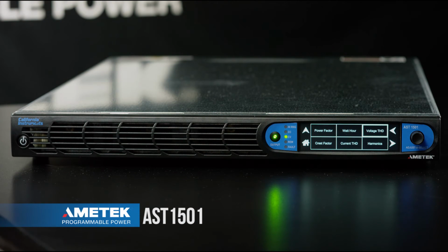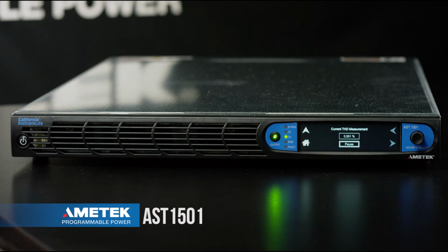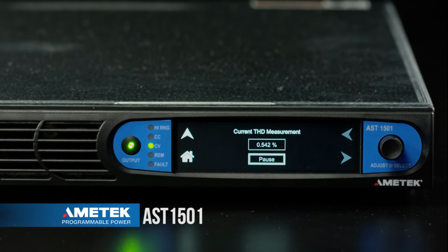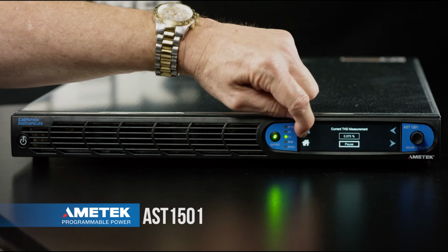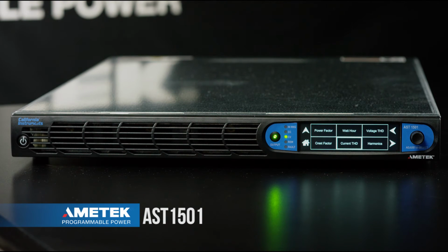We can also look at current harmonic distortion. Similar to the voltage harmonic distortion display, we have a pause key which allows us to grab a moving value in case of a dynamic load. Going back to the previous screen. Next, we'll select a watt hour measurement.